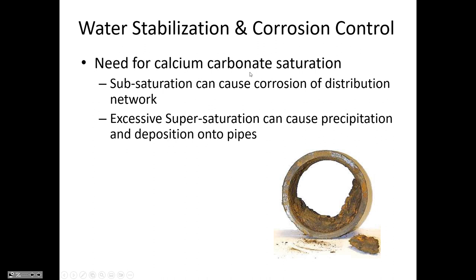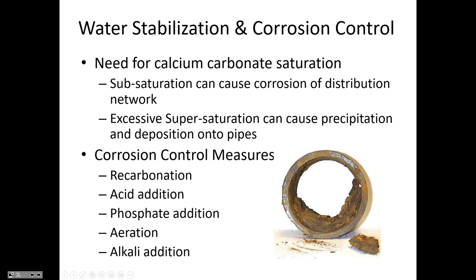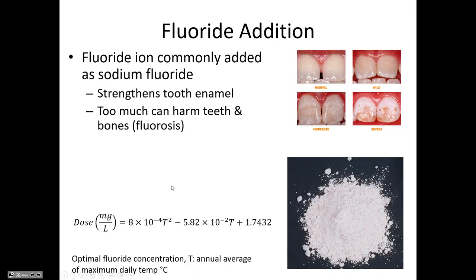Corrosion control can be achieved by having the appropriate amount of carbonate in solution because you want to have a little bit of calcium carbonate coming down and coating the walls of the pipe, but not too much. Because if you have too much accumulation of scale in the pipe, it reduces the capacity. So you can control corrosion by keeping the pH in appropriate range with the addition of CO2 or adding acids, phosphate, and the addition of other things.